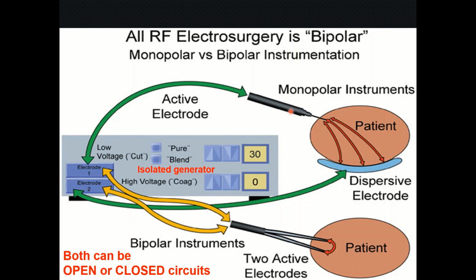Now what would bipolar do? See, this is one electrode, and here the current comes from here, takes a very short course inside the patient, and the second prong of the electrode picks it up and brings it back. So here both the poles are in your electrode, so this is basically a bipolar instrument. So monopolar, remember, is an instrument which only brings the current to your body. It doesn't take it back. Bipolar is one which both brings the current to your body and takes it back from the body, right?